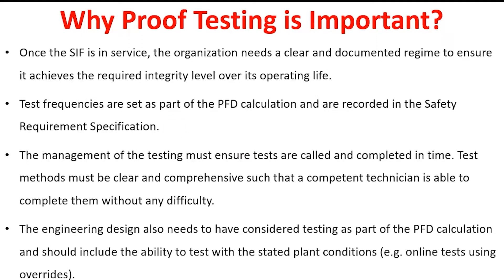The test frequency is arrived at through a calculation based on the probability of failure on demand, and it will determine what kind of configuration is required for the instruments, such as 1 out of 1, 1 out of 2, 2 out of 2, 2 out of 3, etc.